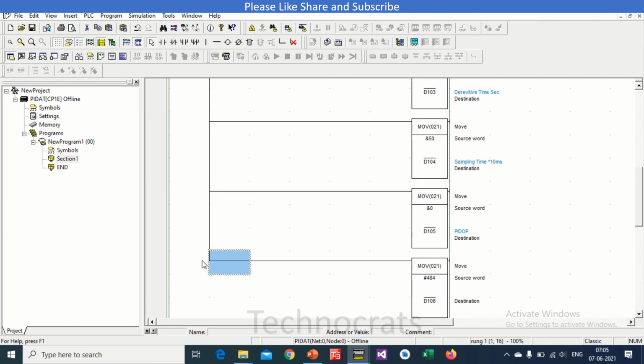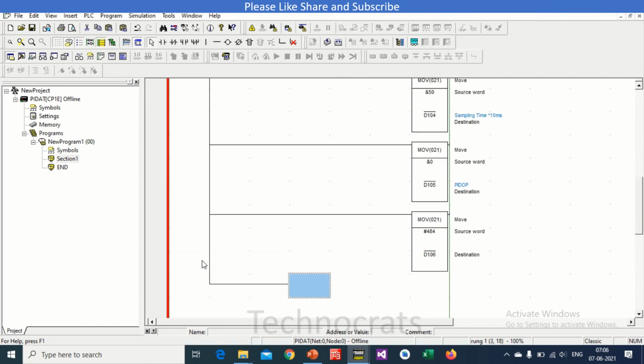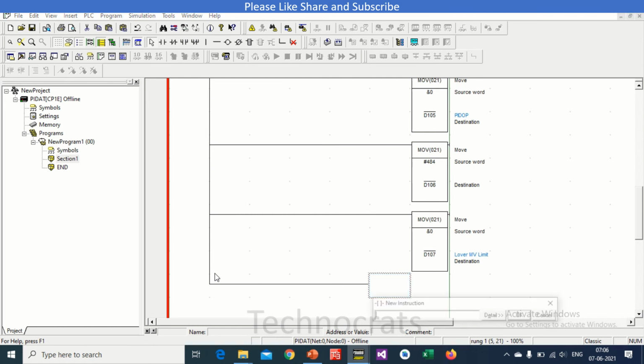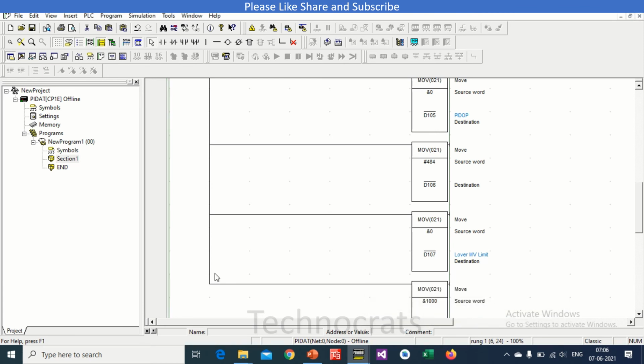After this, I have D107. That is for the lower limit of MV. Let me put 0 here. MOV #0, or you can say &0, to D107, and this is lower MV limit. Now after this, you have the upper limit for MV, so that your MV does not go beyond any limit. So I will just put here 1000 to D108, that is your upper limit.